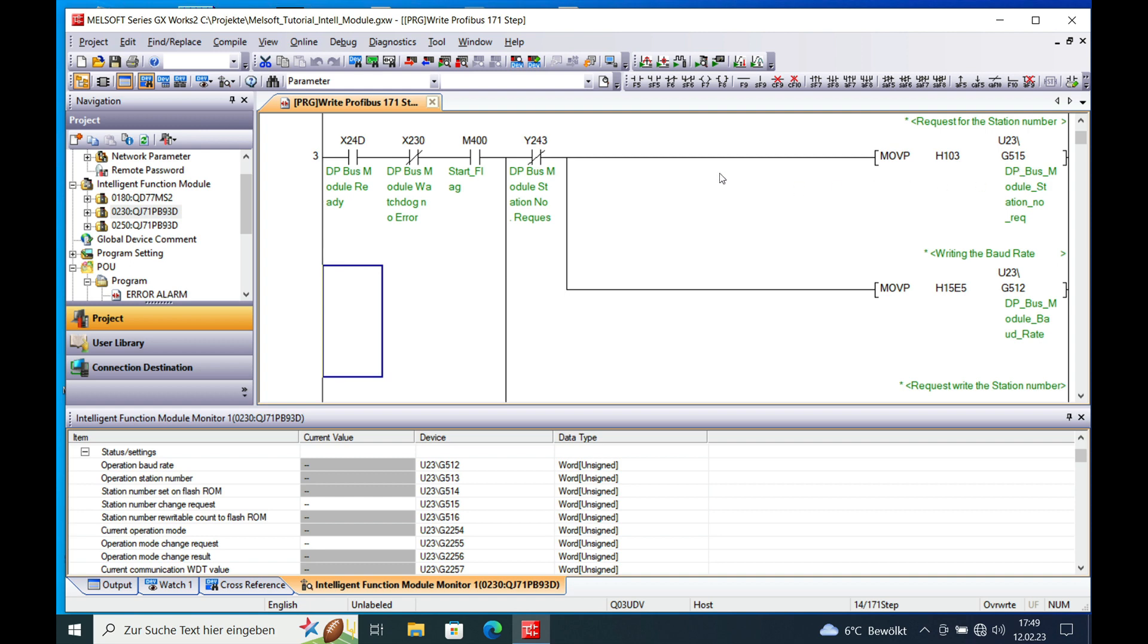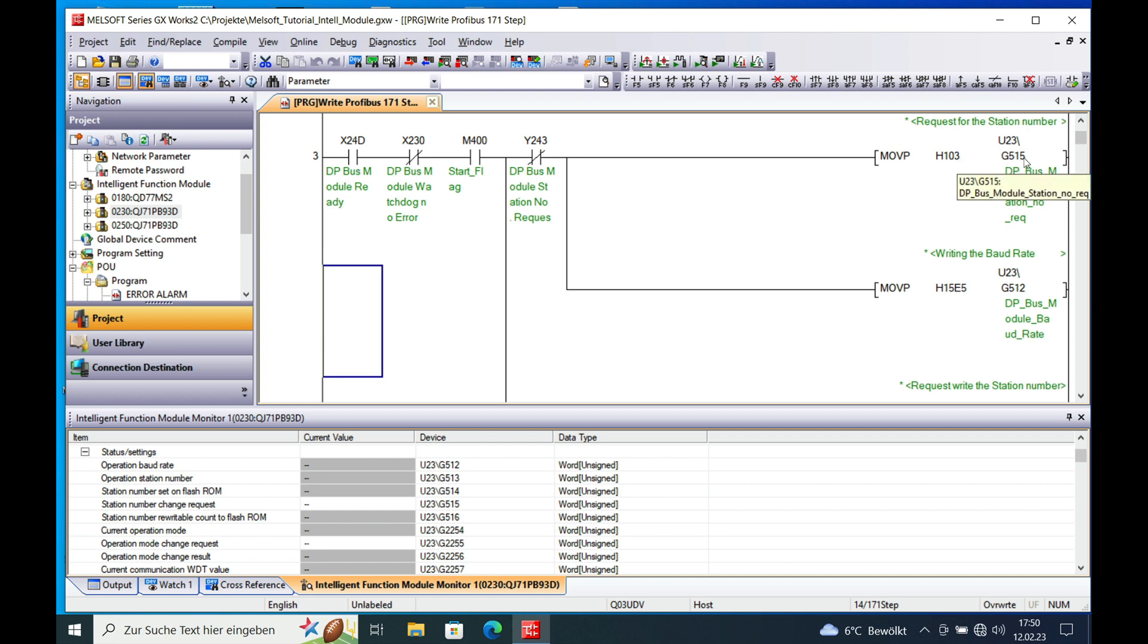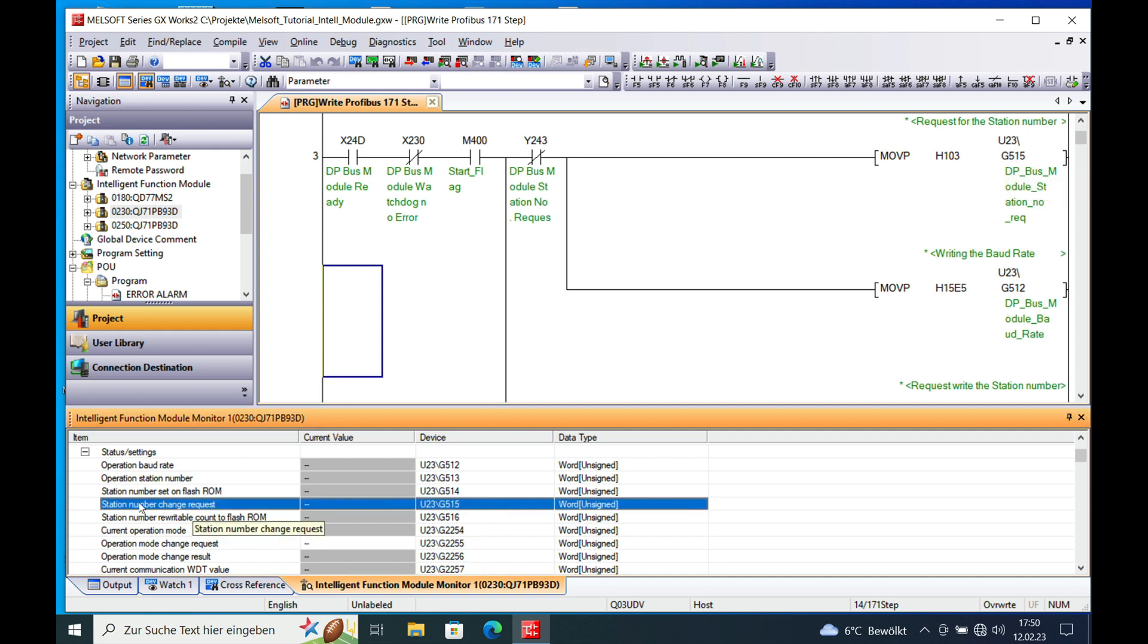And then in order to do this you have to move your station number that you actually want to use. You have to double check that with your master on the other side of the bus. And then in this case it is just a number 3. And this you need to move to the buffer memory G515. You can see this right here.